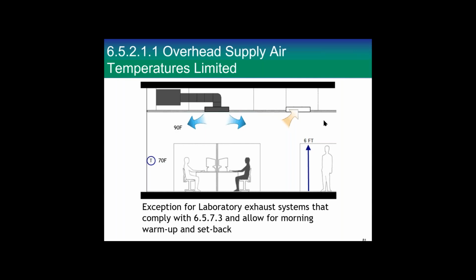You can do anything you want to with the heat, how hot it is. And in ASHRAE 62, it's only 15 degrees, so you would have to use 85. Now, we are finding that we can heat with much cooler air than we thought we could. So that 85 number is not outlandish. We're successfully heating with much cooler air.